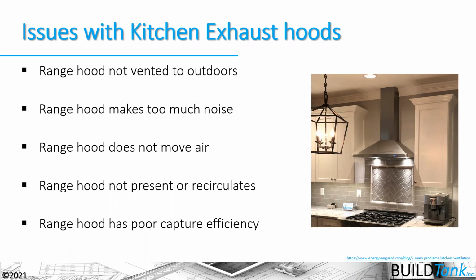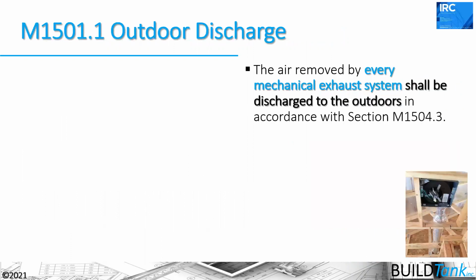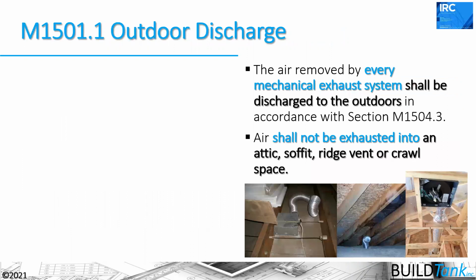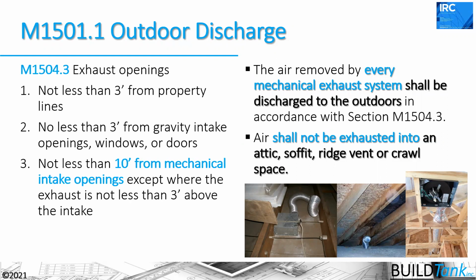So when you're looking for hoods now, they are starting to rate the hoods with a capture efficiency number. The better the capture efficiency, the better the hood is actually going to work. But regardless of the hood that you have, and regardless of the type of spot ventilation we're talking about, everything needs to be discharged to the outdoors here. So you can't discharge into an attic or a soffit or a ridge vent or a crawl space or any of those locations. You've got to take that duct all the way to the outdoors, and you've got to locate that exhaust duct away from any intake air duct as well.